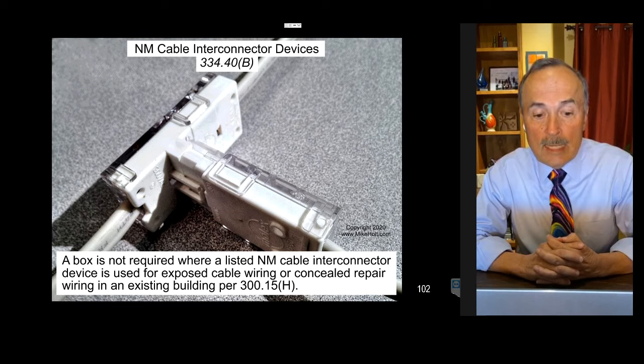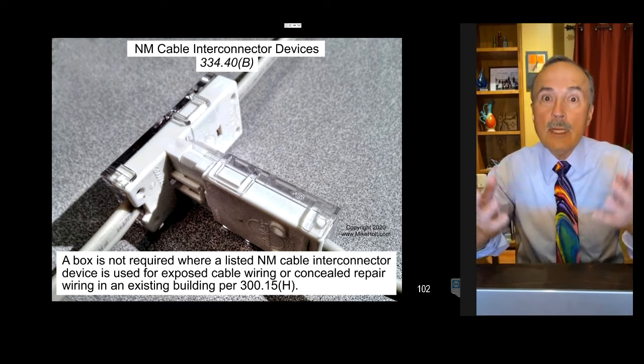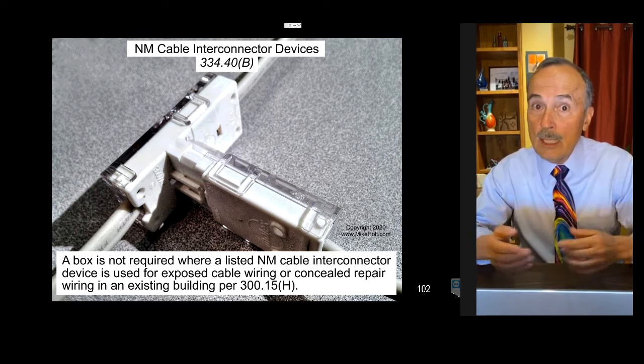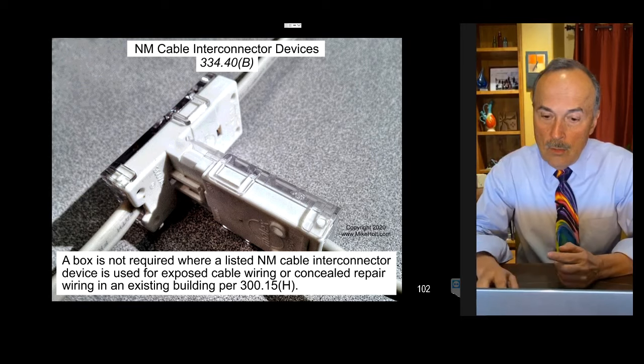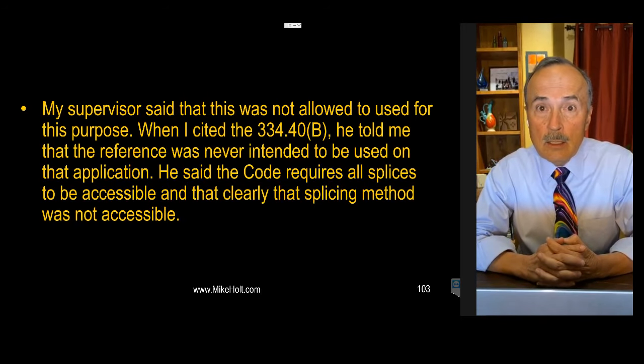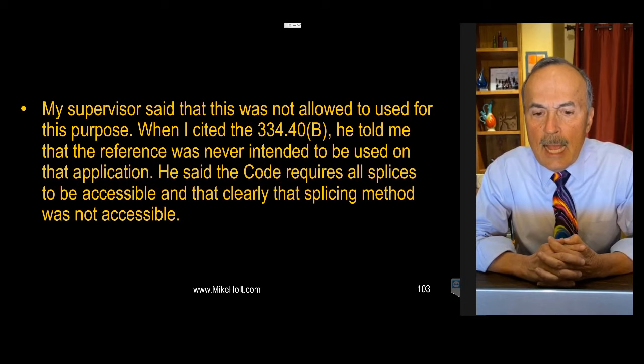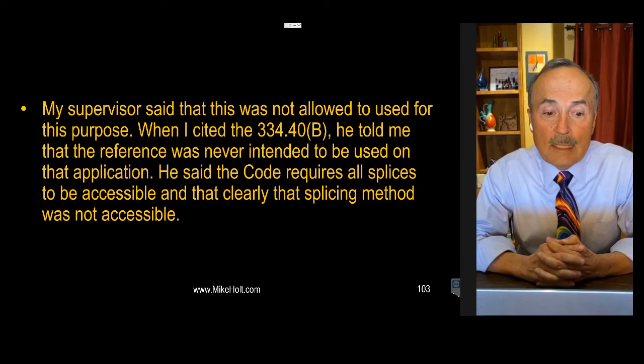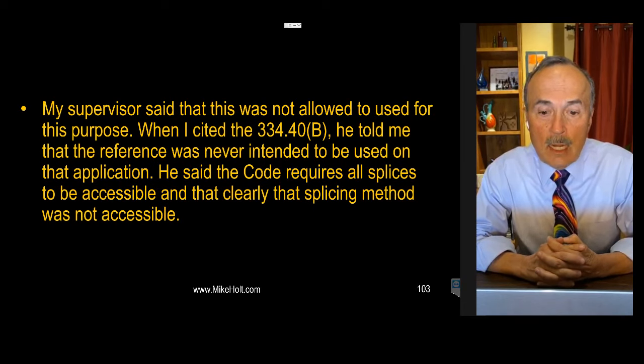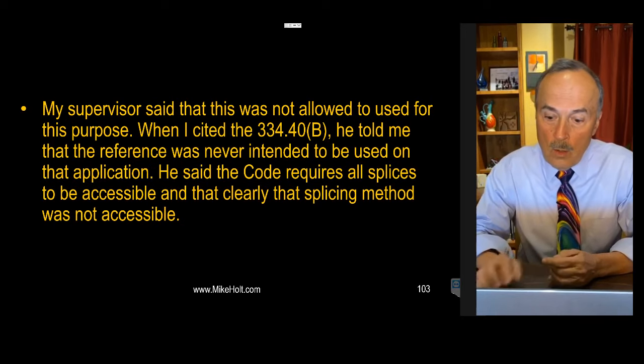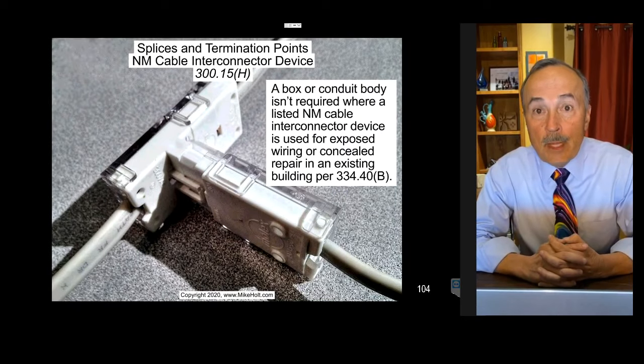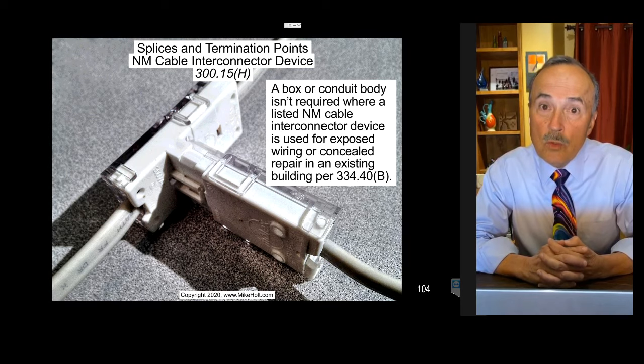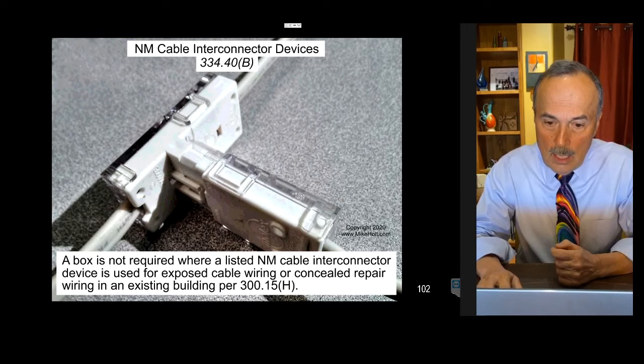Okay, let me read 334.40(B). A box is not required where a listed NM cable interconnector device is used for exposed cable wiring or concealed repair wiring in an existing building. Exposed or concealed. Well, that's pretty much everything there is, right? I don't know anything else. I guess you can't put it in the ground. So I'm thinking, okay, well, that guy's an idiot to even make that statement. He said that the code requires all splices to be accessible and that clearly that splicing method was not accessible.